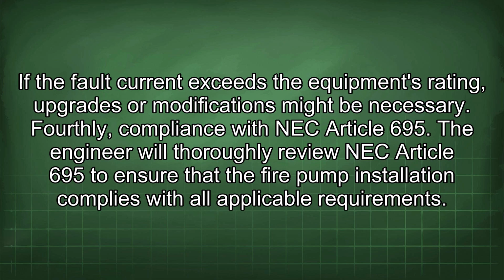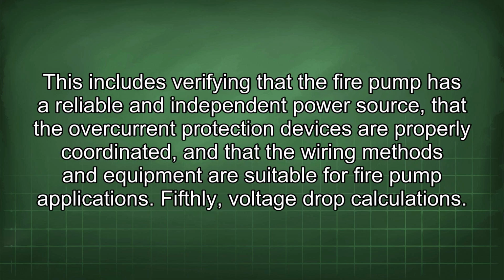Fourthly, compliance with NEC Article 695. The engineer will thoroughly review NEC Article 695 to ensure that the fire pump installation complies with all applicable requirements. This includes verifying that the fire pump has a reliable and independent power source, that the overcurrent protection devices are properly coordinated, and that the wiring methods and equipment are suitable for fire pump applications.